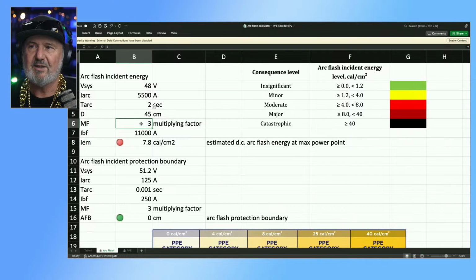The multiplying factor is to do with whether it's installed in the open, in a building, or in an enclosure. So I'm going to put it in an enclosure, which gives the highest multiplying factor, 3. So I've got a battery box, and it focuses that arc flash incident energy. And you'll see that we got up to 7.8 cal.